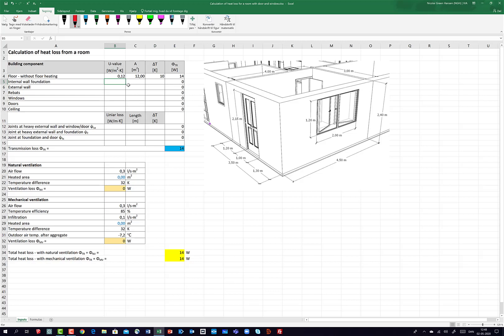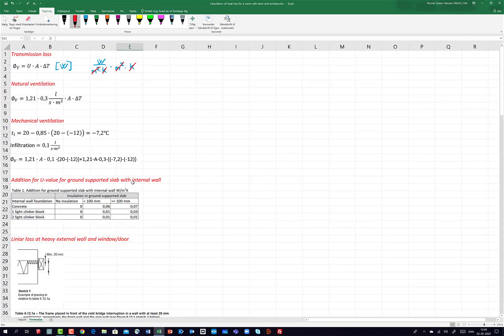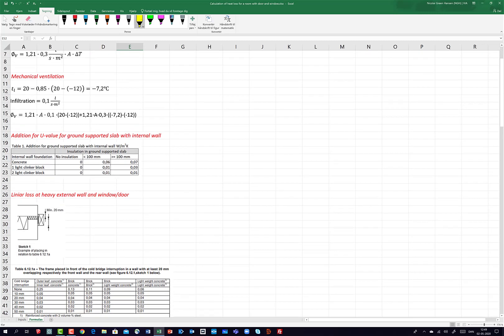I also have a heat loss because of the internal walls. Here inside, this also causes a heat loss. I go to the tab formulas, and here I can see it. You are asked about the insulation in the ground support slab: no insulation, less than 100 mm, or more than or equal to 100 mm. Today I'll use more than 100 mm of insulation. The unit is Watts per square meter per Kelvin, so it's a U-value.